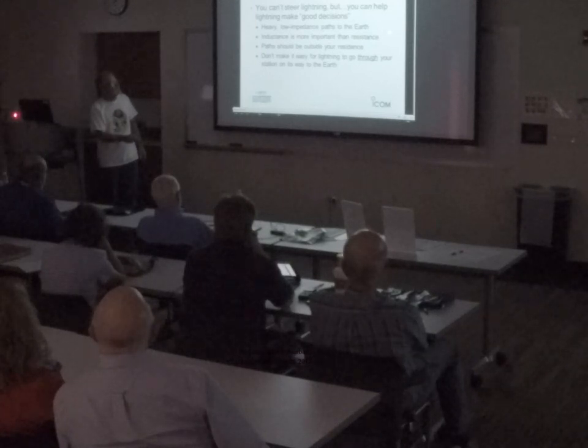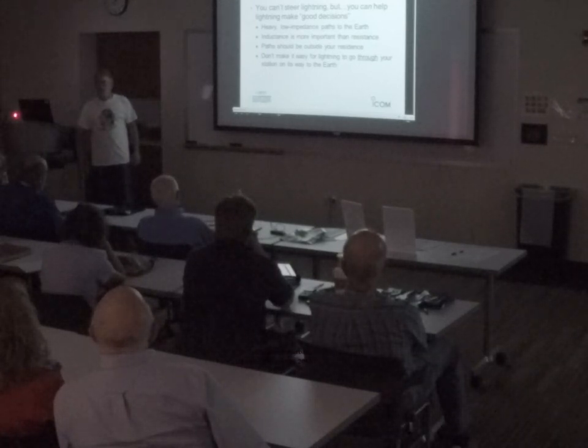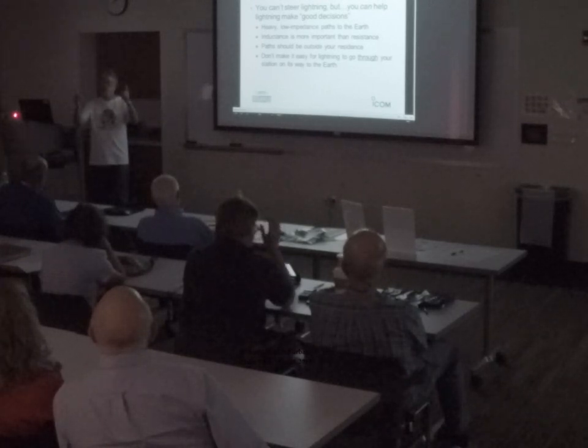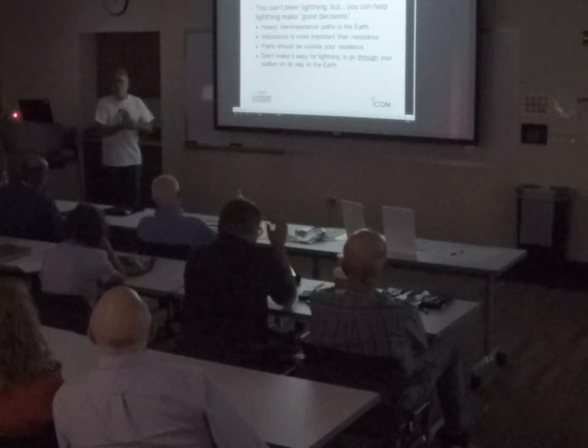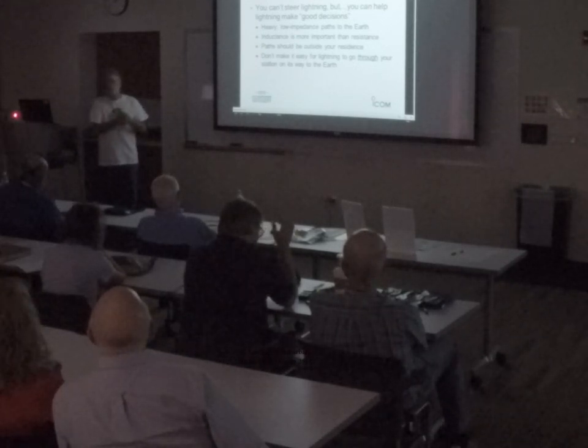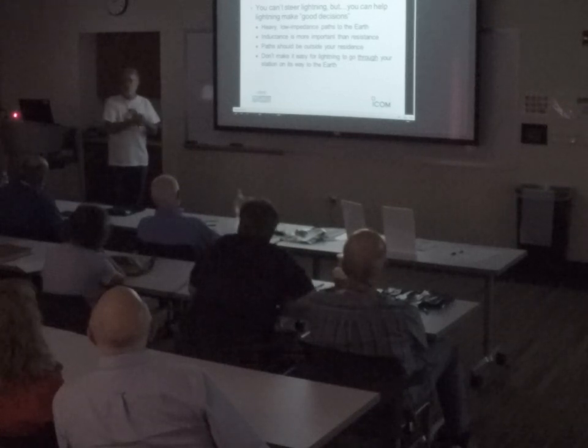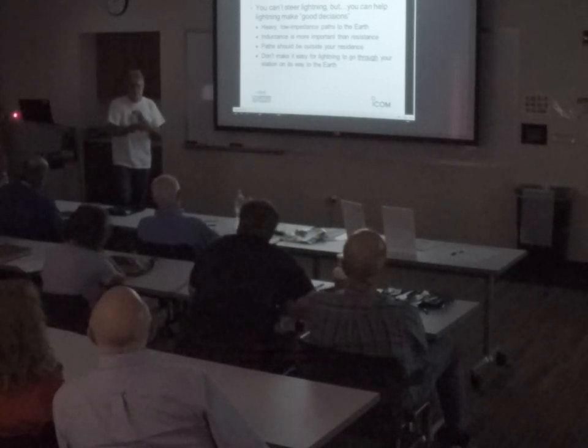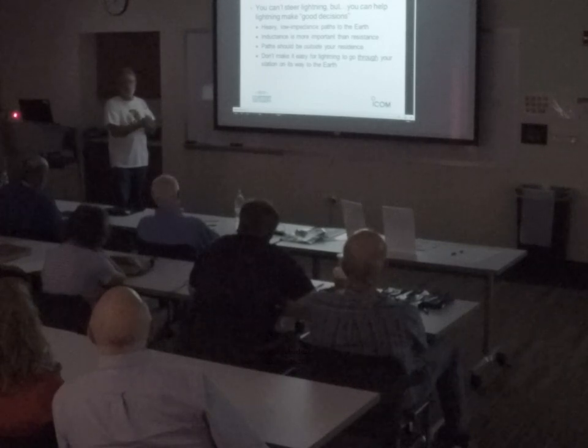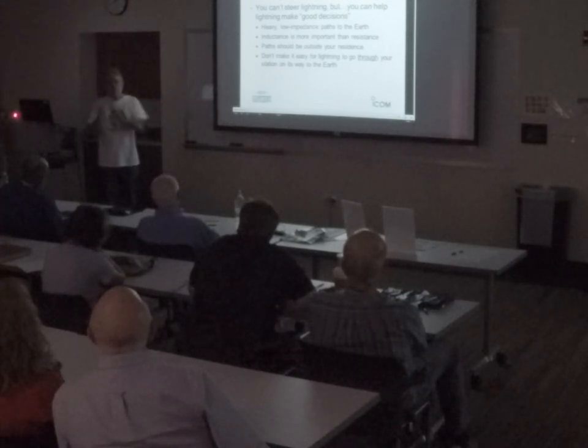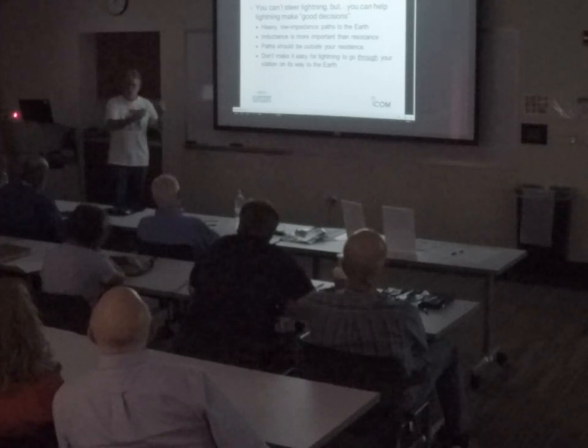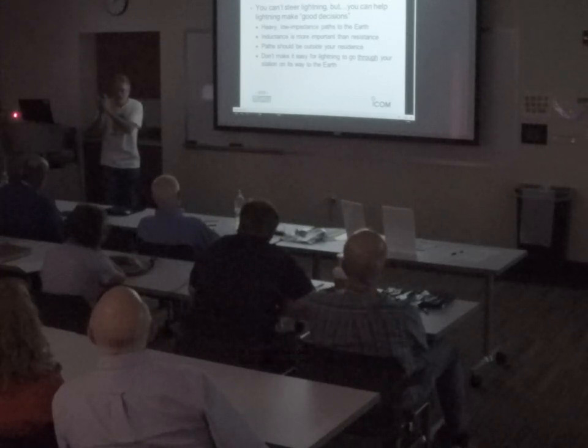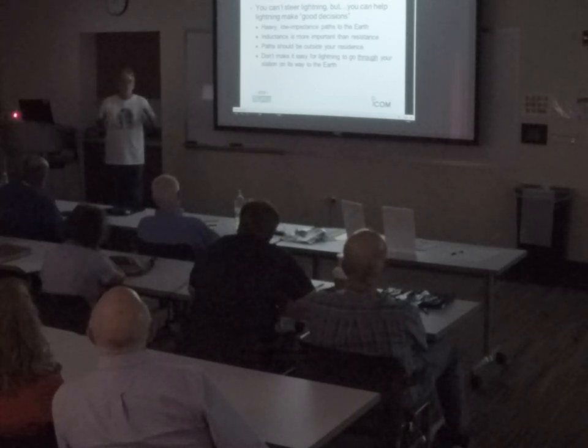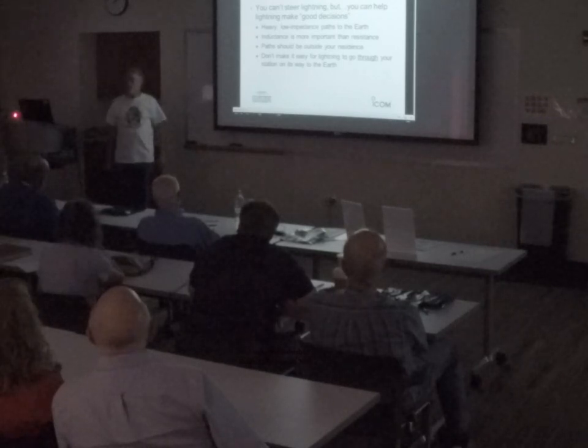Inductance is really much more important than resistance here. Even a straight piece of wire, one foot long, has a nanohenry or so of inductance. When you hit that thing with a kiloamp pulse rising at 20 to 30 kiloamps per microsecond, that's a big change. Voltage is inductance times rate of change of current. So if you've got a big rate of change of current, even a little tiny nanohenry can cause that one foot of wire to have hundreds of volts from end to end.